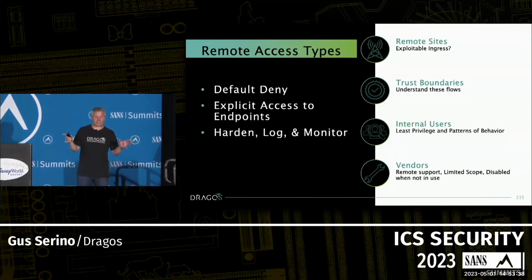somebody stole an RTU from a customer, and it made me think, wow. Take an RTU, a remote terminal unit that's monitoring some value out in the field, usually with, for example, a cell modem in it. Somebody steals that RTU, powers it up. Now they have a cell modem into your environment. They know your IP address scheme from the devices that are on the RTU. Do you have an ability to detect that? Do you have an ability to know who you need to call to shut down that particular access?